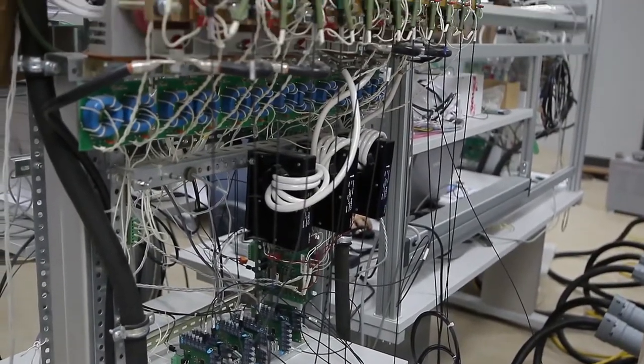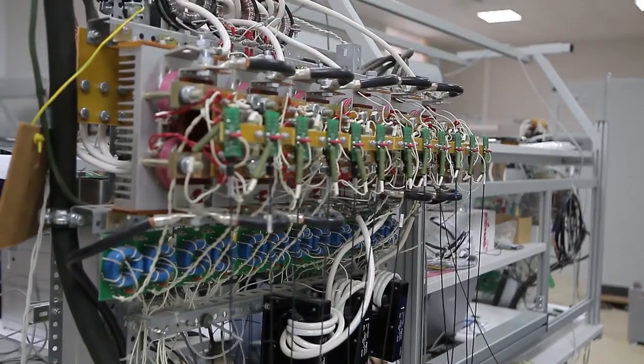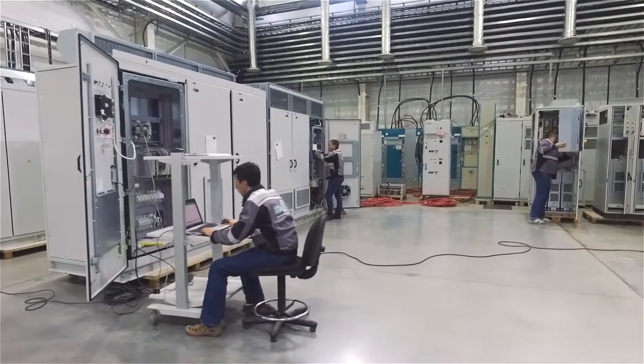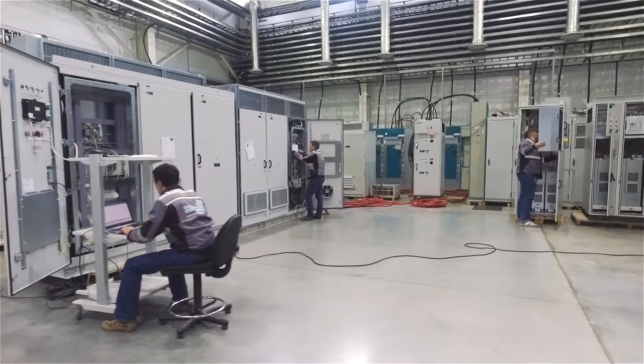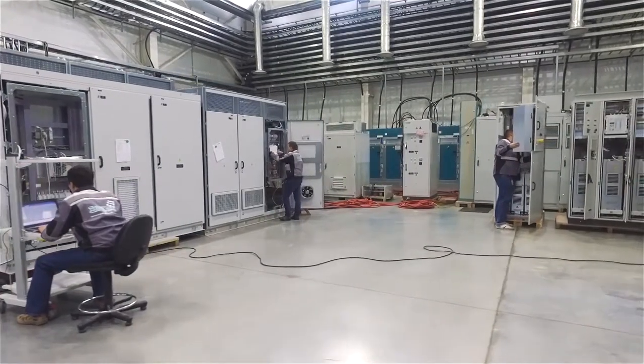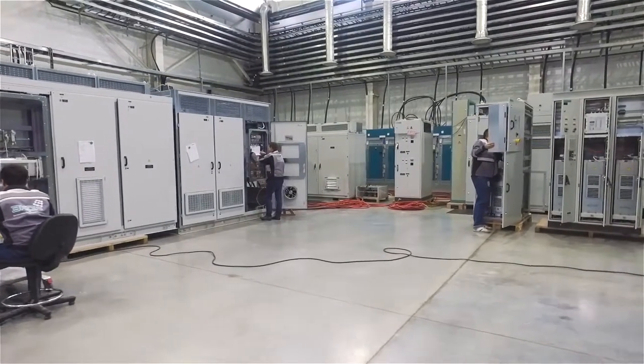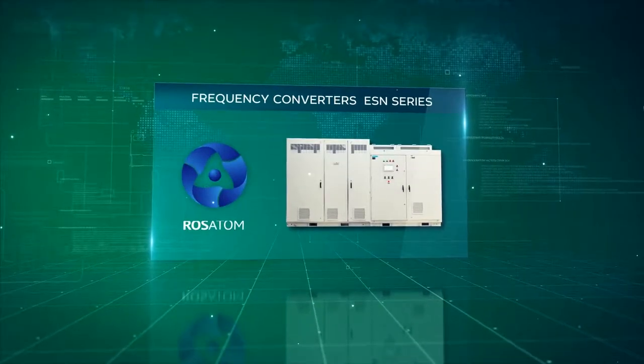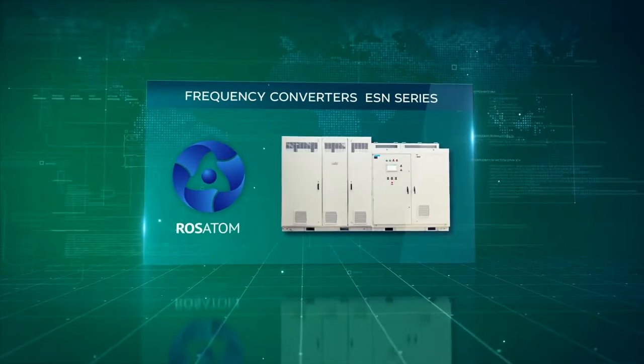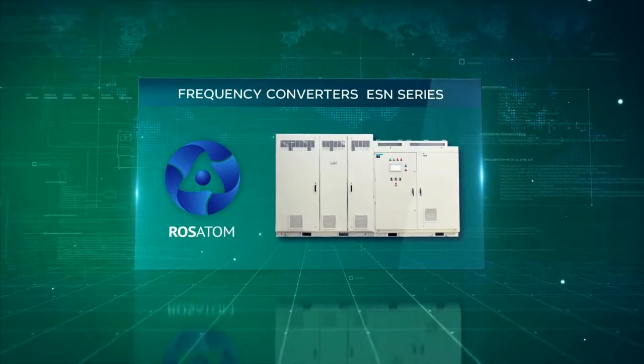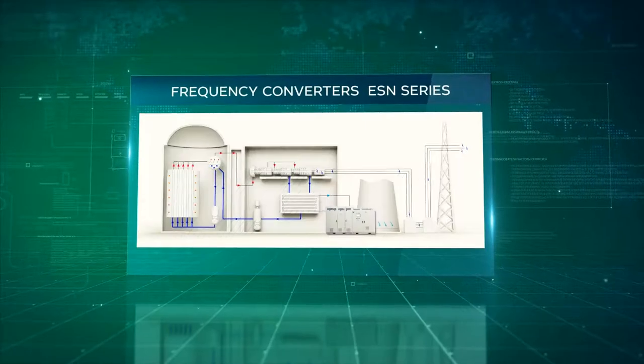Frequency converter development for motors up to 12.5 megawatts is underway. A high voltage frequency converter system based on a transformerless scheme is being developed with the possibility of energy recovery to the power line. As a result of Rosatom testing, frequency converters of the ESN series were recommended for installation along with unit pumps for nuclear reactor cooling.